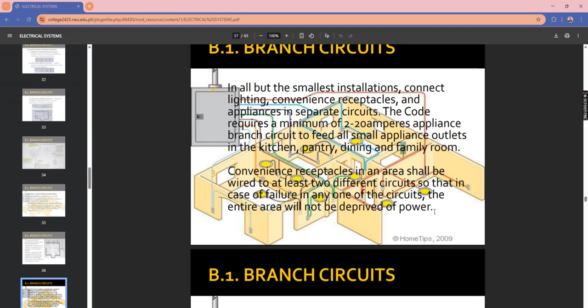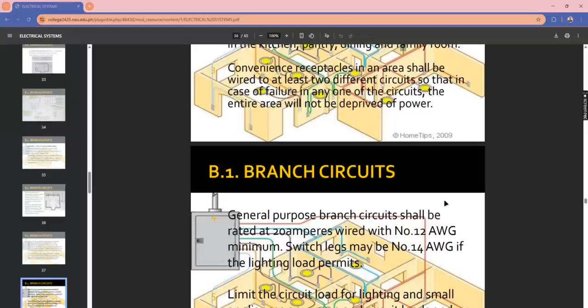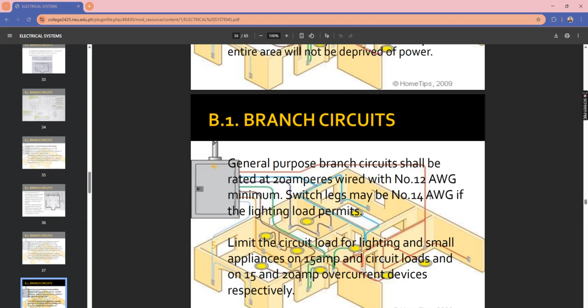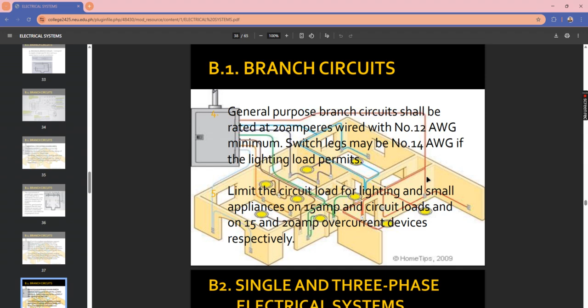Convenience receptacles in an area should be wired on at least 2 different circuits, so that in case of failure in any of the circuits, the entire area will not be deprived of power. So, kailangan meron siyang backup or separate circuit talaga. The general purpose branch circuit shall be rated 20 amps with a wire of number 12 AWG minimum. Switch legs must be number 14 AWG if the lighting load is permitted. Ito yung mga sizes of wire, no, na gagamitin.